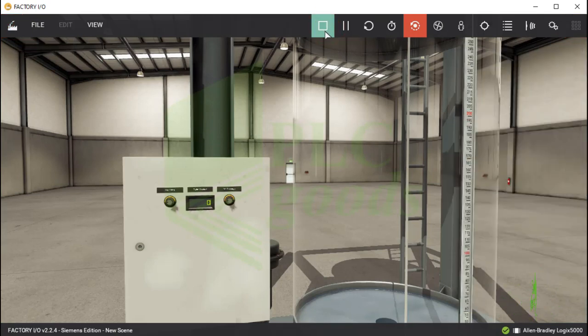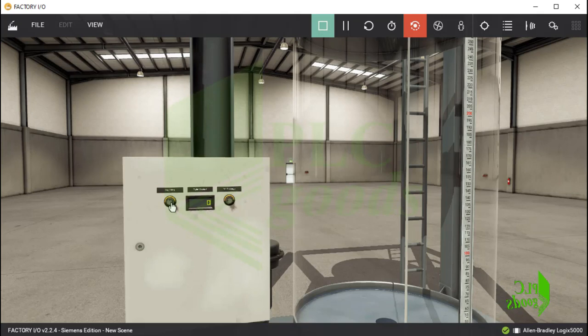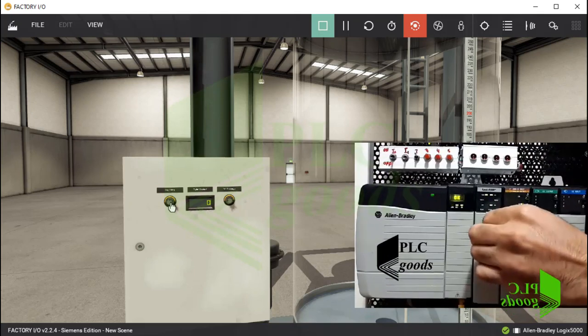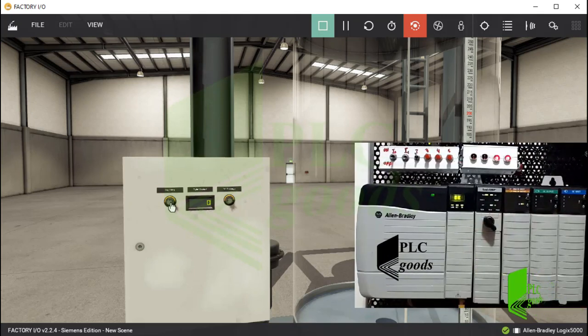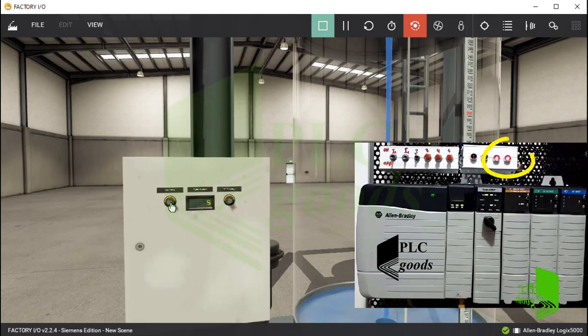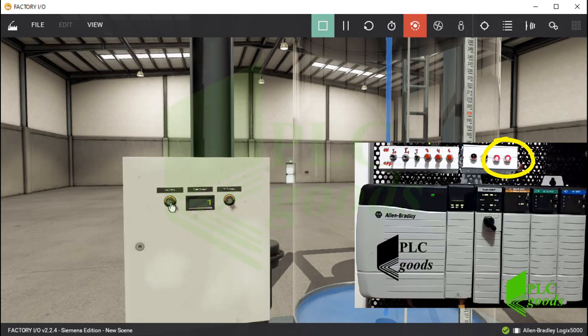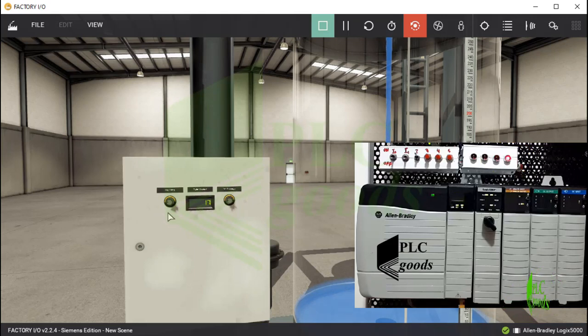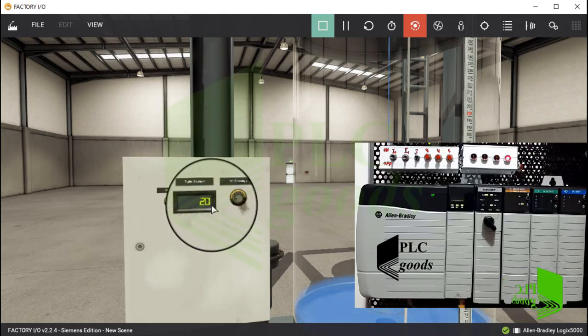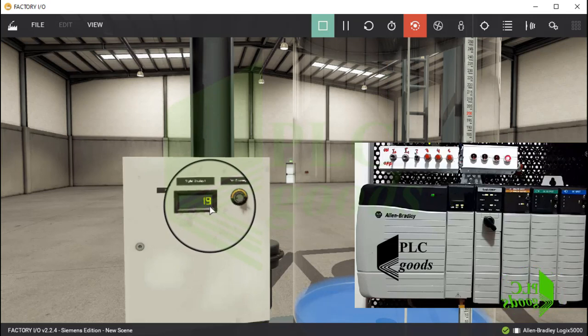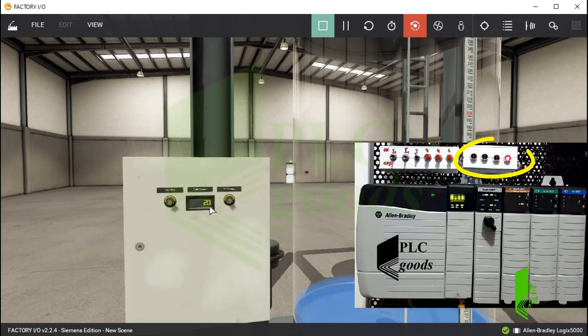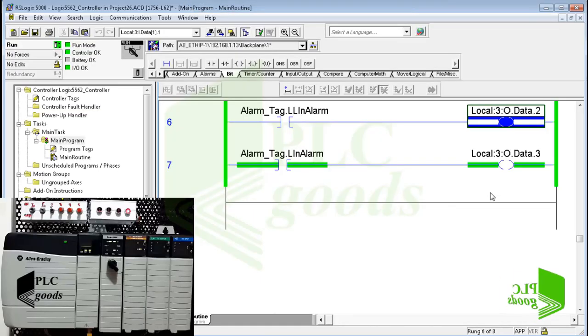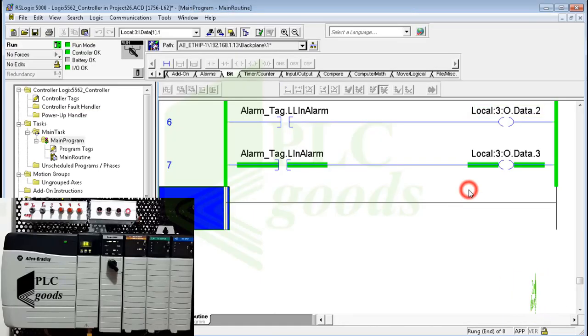Let's go to test the project. First, let me open the filling valve. Well, I must change my controller mode to run mode. As you see, in the beginning when the tank is empty, these signal lamps are turned on because two alarms have been activated inside the PLC program. Now the water level is 20 centimeters. The level is low, but it's not under 10 centimeters. So only one alarm is activated.